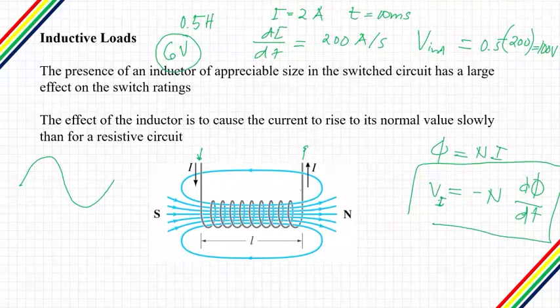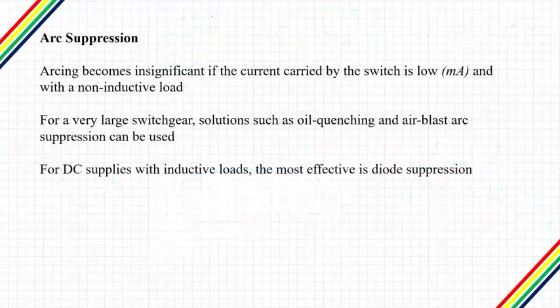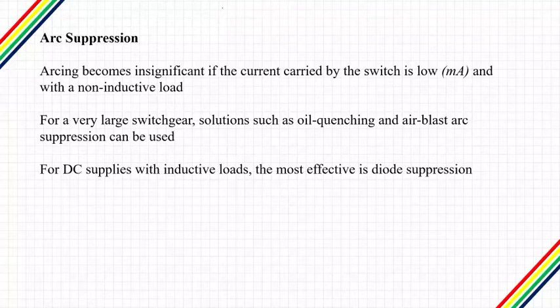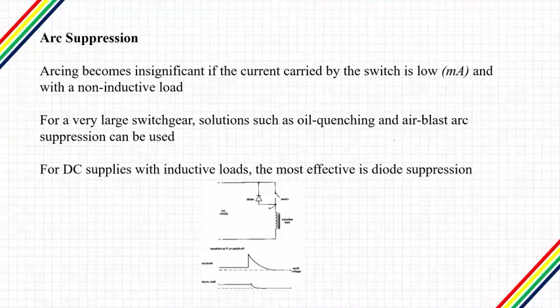This value of 100 volts is comparatively small, but if the circuit is rated at only 6 volts DC, then the presence of 100 volts across the switch contacts will cause a considerably greater amount of arcing. Arcing becomes insignificant if the current carried by the switch is low — probably at milliamperes level — and with a non-inductive load. But when dealing with DC supplies and inductive loads, arc suppression cannot be neglected. For this type of circuit, the most effective method of arc suppression is diode suppression, as shown in the diagram.